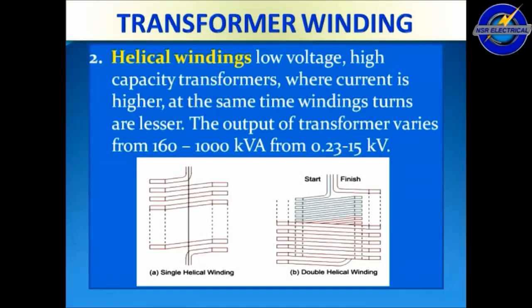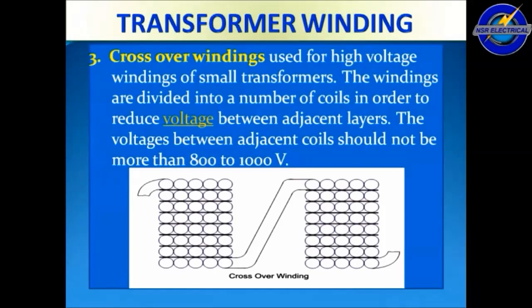The second one is helical windings. Helical windings are used in low voltage, high capacity transformers where current is higher and at the same time the number of winding turns is lesser. The output of the transformer varies from 160 to 1000 kVA and from 0.23 to 15 kV.